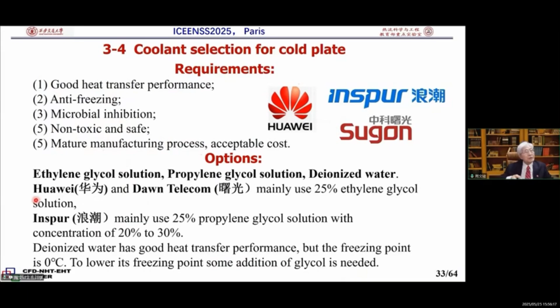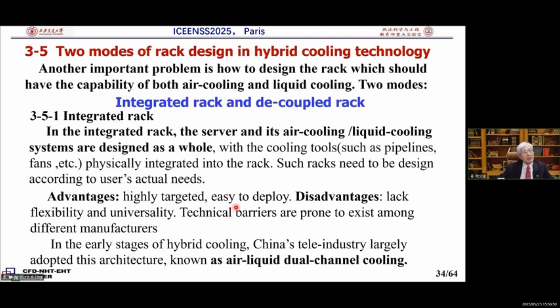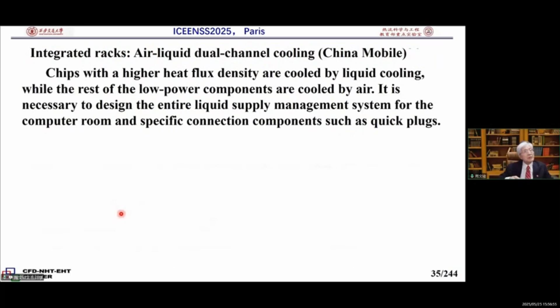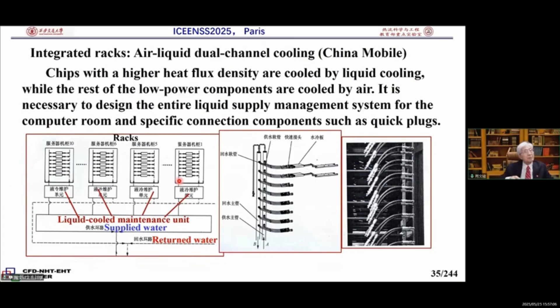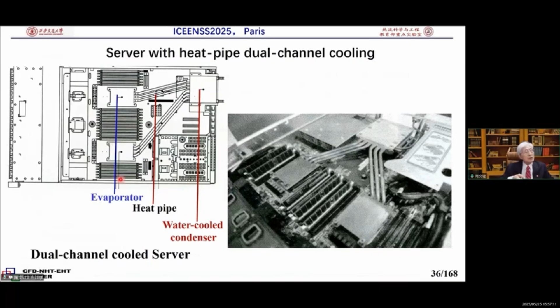Now, for the modes of supplying the rack for hybrid cooling, there are two modes: one, an integrated rack; second, a decoupled rack. In the integrated rack, the server and its air cooling and liquid cooling systems are designed as a whole. The advantage is high integration. The disadvantage is less flexibility and universality, and technical barriers are prone to exist among different manufacturers. This is the integrated rack in China Mobile. Here are a lot of quick plugs for cooling water, and here are different racks. This is a server. These two are cooled by the cold plate, other components by air.